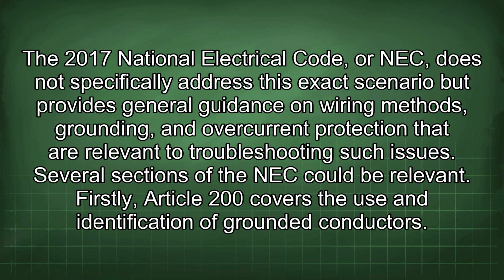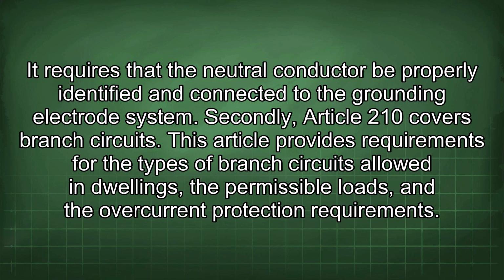The 2017 National Electrical Code, or NEC, does not specifically address this exact scenario but provides general guidance on wiring methods, grounding, and overcurrent protection that are relevant to troubleshooting such issues. Several sections of the NEC could be relevant. Firstly, Article 200 covers the use and identification of grounded conductors. It requires that the neutral conductor be properly identified and connected to the grounding electrode system.